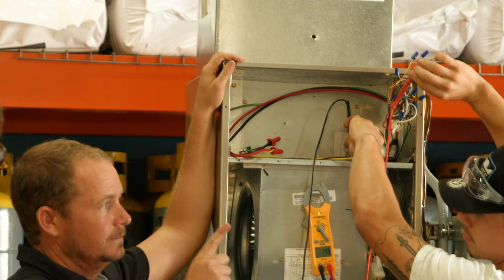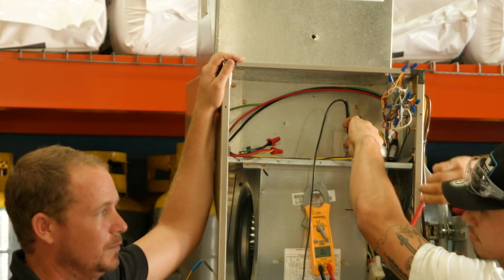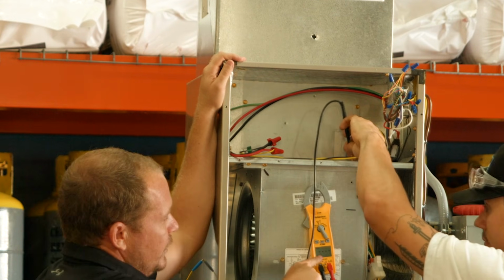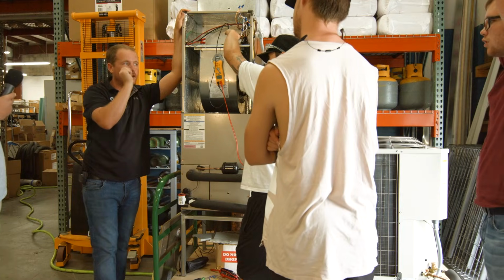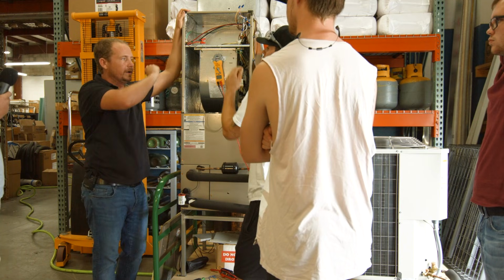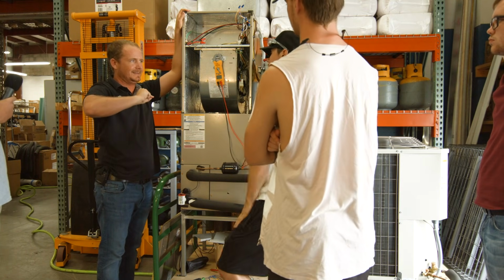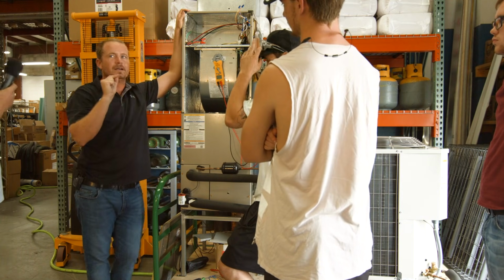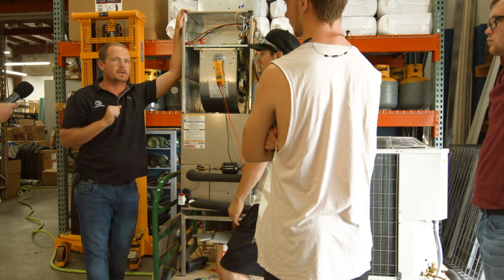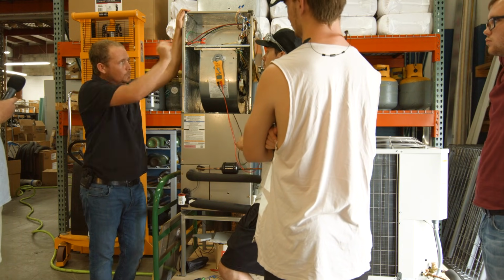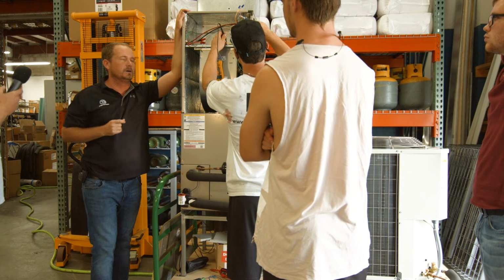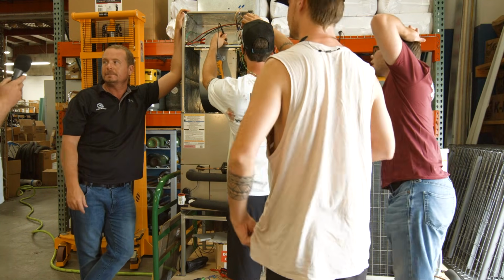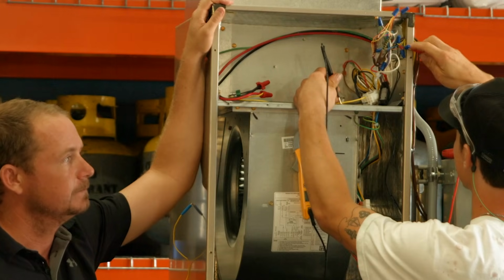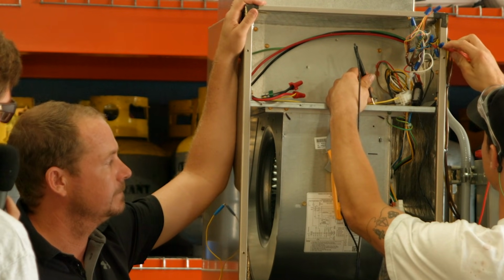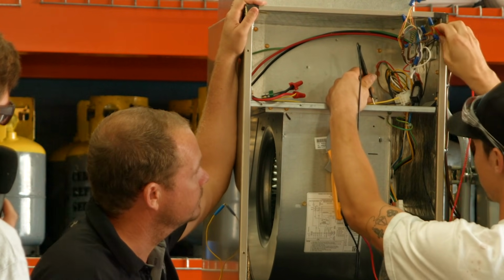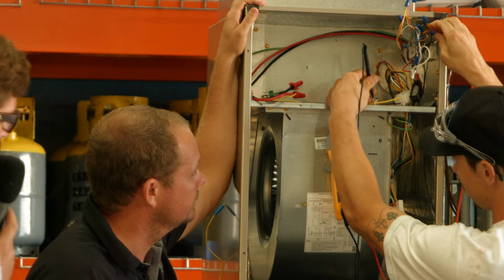Okay, so this is why this is a pro move, because you're noticing now you're measuring the ohms of the load, because you're going through the entire circuit now. Exactly. So what you're looking for is not 14 ohms, you're looking for something much closer to 0. So go through each one and find the one that's much closer to 0. On a system like this, I'd be most concerned with stuff in single digits, because usually the compressor contactor is the biggest load and it's around 10 to 15.